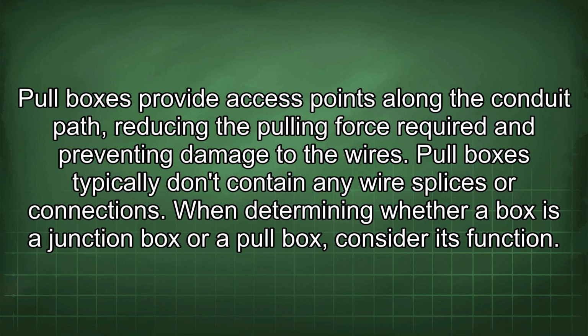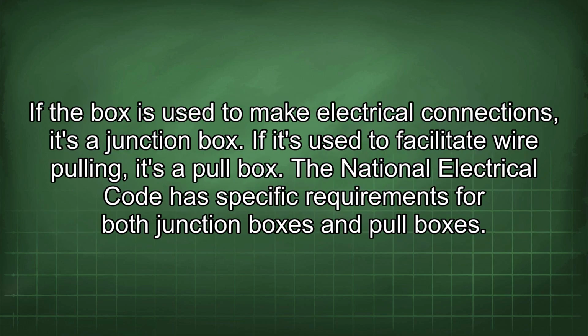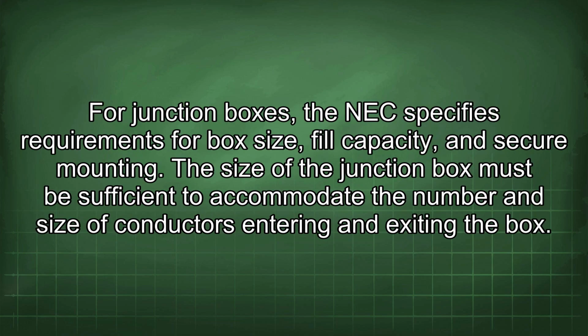When determining whether a box is a junction box or a pull box, consider its function. If the box is used to make electrical connections, it's a junction box. If it's used to facilitate wire pulling, it's a pull box. The National Electrical Code has specific requirements for both junction boxes and pull boxes. For junction boxes, the NEC specifies requirements for box size, fill capacity, and secure mounting.